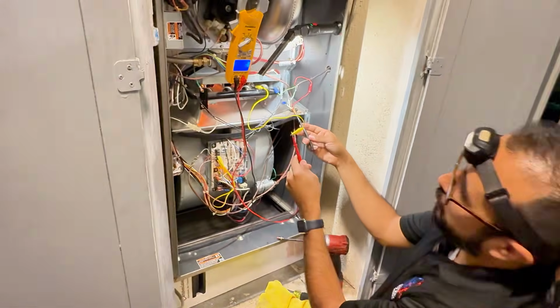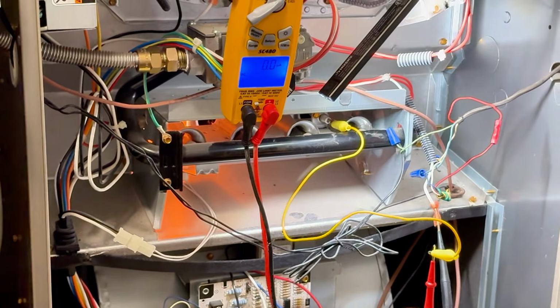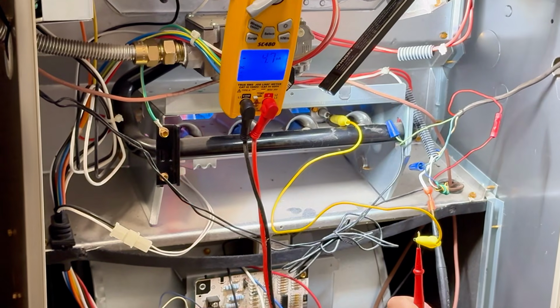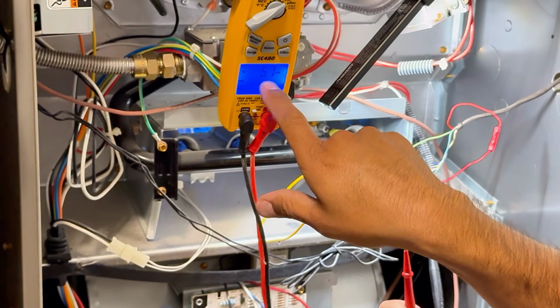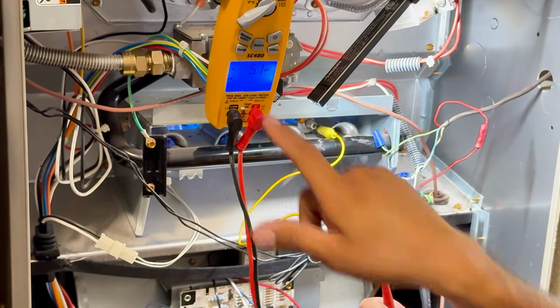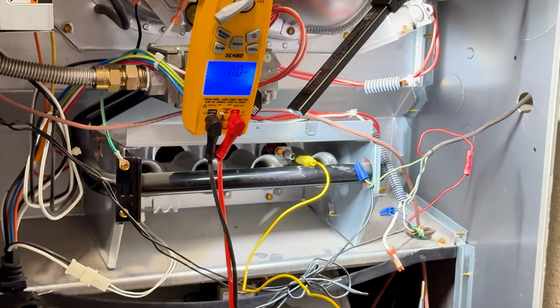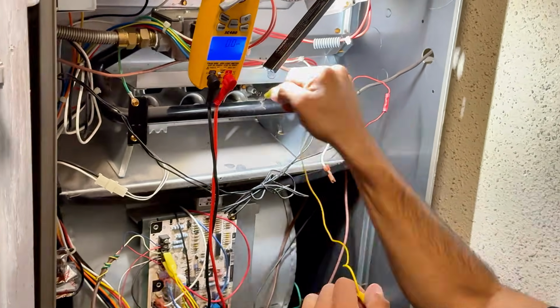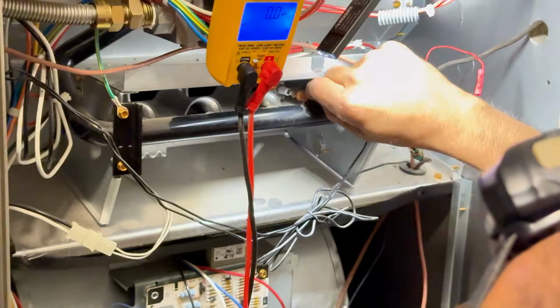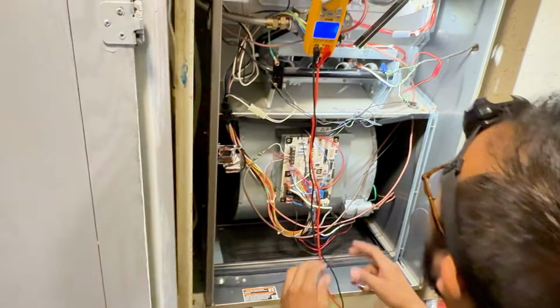The only thing I regret not showing you, and I did check, was the squirrel cage. That squirrel cage where your indoor motor is at could be dirty and have dust, and even a little bit can mess your CFM. But I did check it, it was clean, and that electronic air cleaner helped out as well, it seemed like that filter took most of the hit.